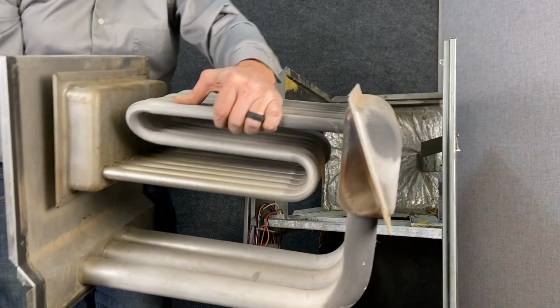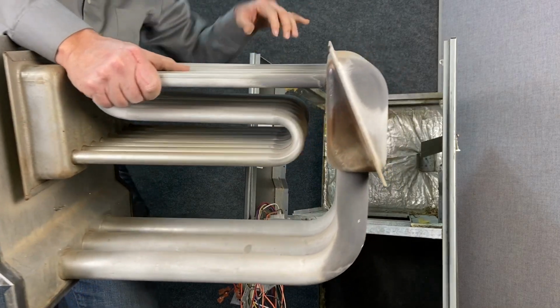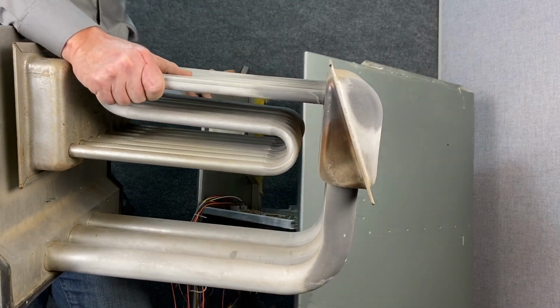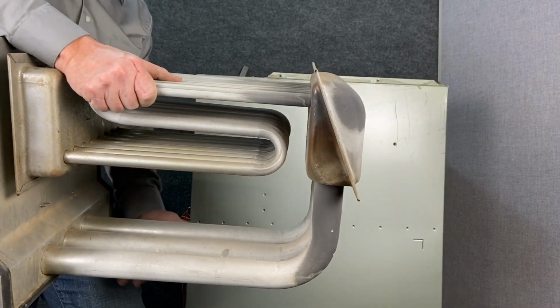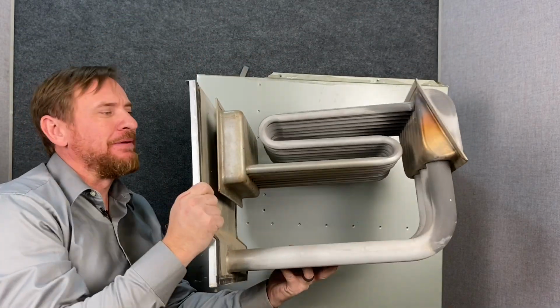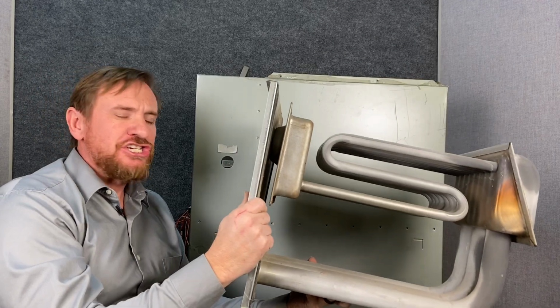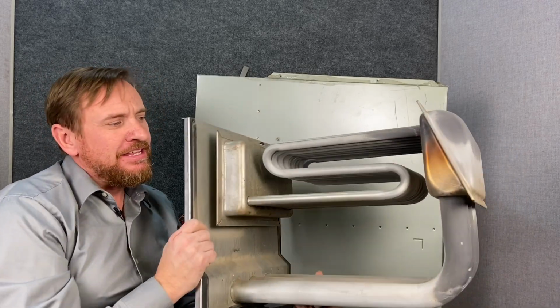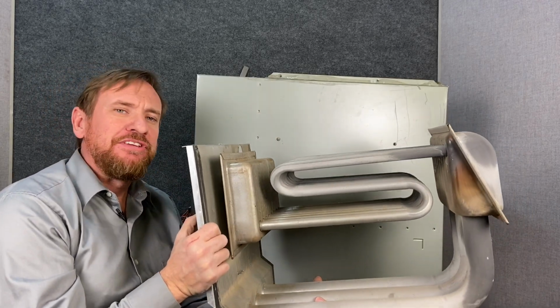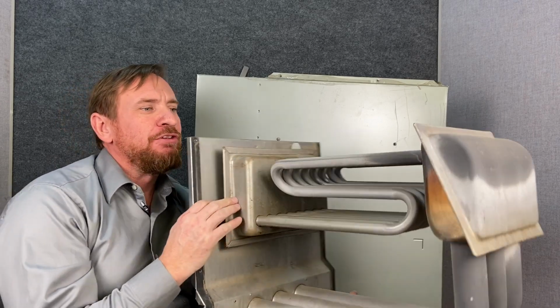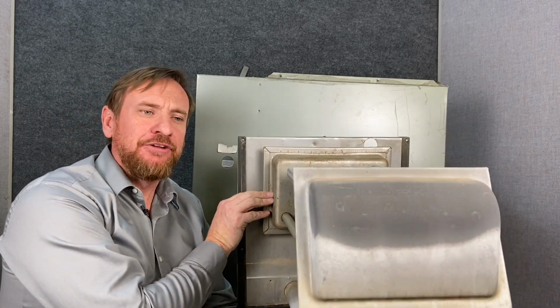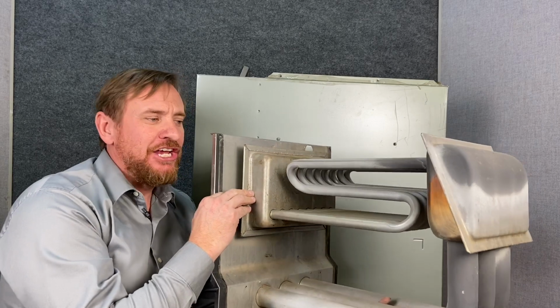Now here we have the heat exchanger itself. This is the guts. So if somebody says, can't you just change out the heat exchanger? The answer is yes, you can, but it does take a significant amount of labor to make sure this happens. So this is our heat exchanger. Everything's built around it. Now these should last a lifetime. Most of these have 20-year warranties on them. And if you set it up, have the proper airflow, the proper maintenance on this, it should last at least 20 years.